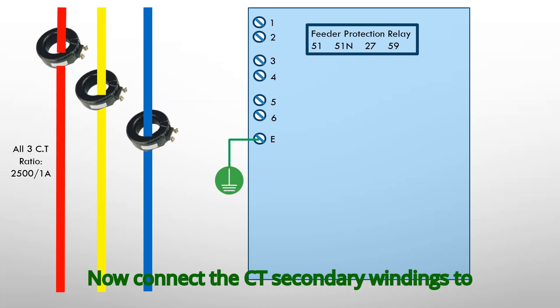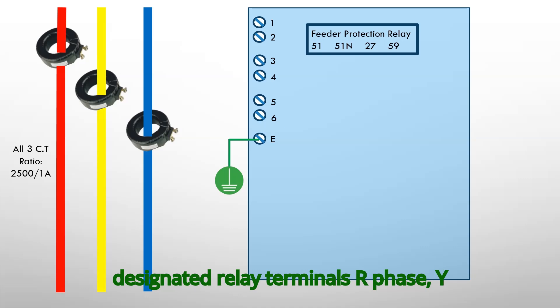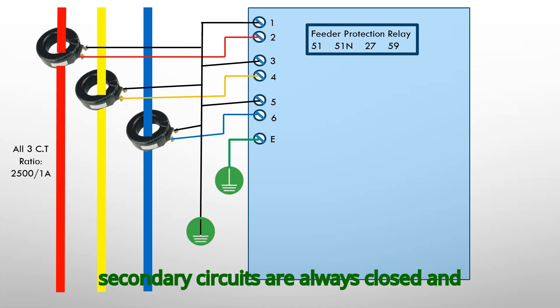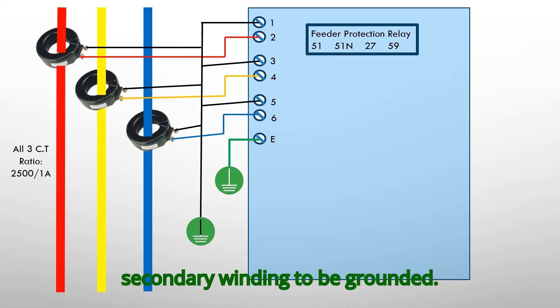Connect the CT secondary windings to the feeder protection relay terminals — R-phase, Y-phase and B-phase. Ensure CT secondary circuits are always closed and never left open. The return supply from the CT secondary winding must be grounded.